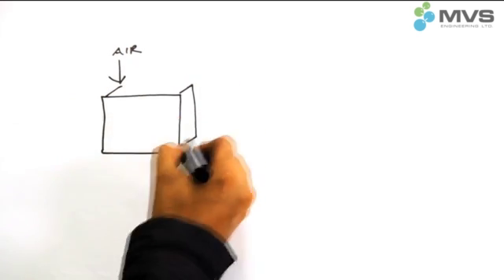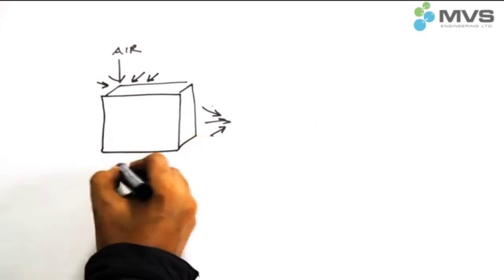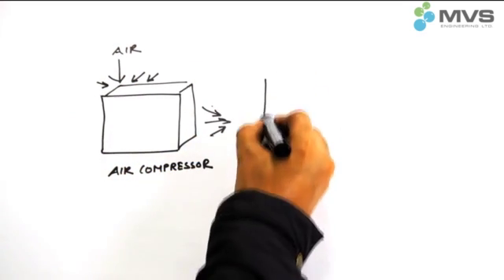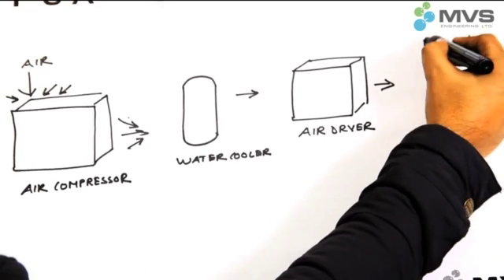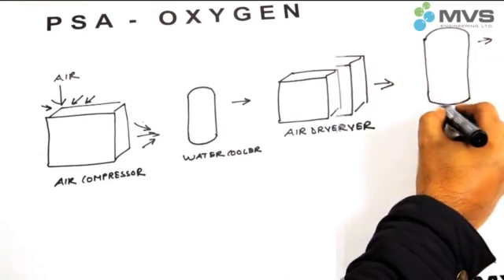In an on-site oxygen generator, the atmospheric air is compressed using an air compressor. This air is compressed and made moisture-free using an air dryer. The dry air is collected in an air receiver tank.